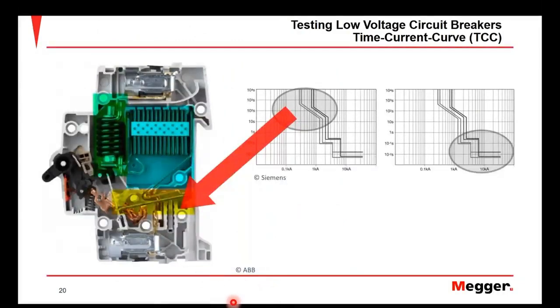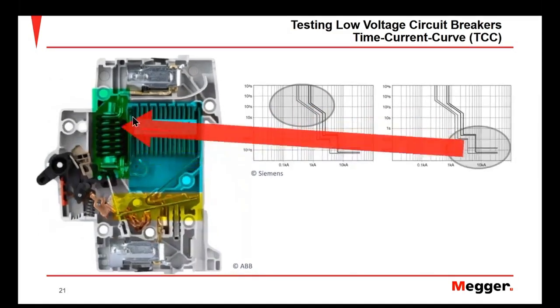This is the physical representation of the mechanical hardware. The overload element — long time and short time — relates to the thermal protective function in the breaker, which works off a heating effect that occurs when a certain amount of current flows. Additionally, there is the physical magnetic mechanism that relates to the instantaneous function of the time current curve.